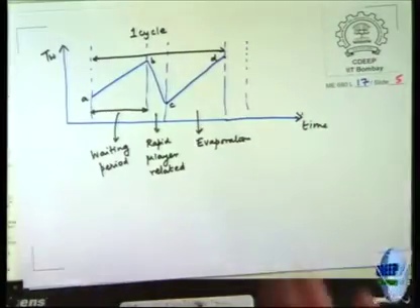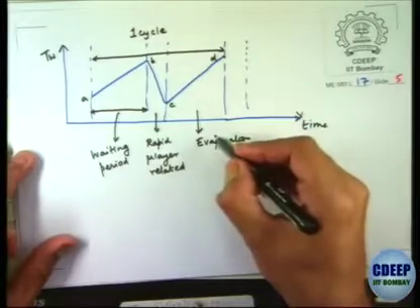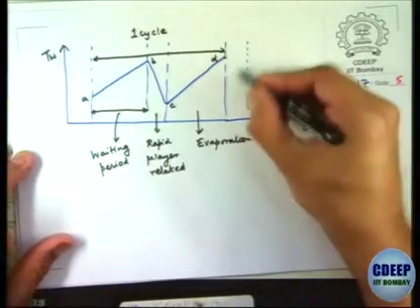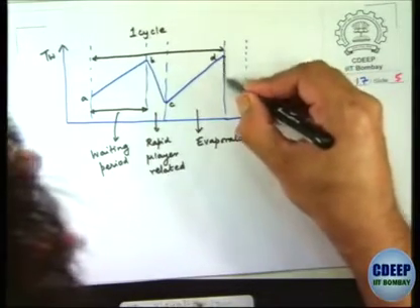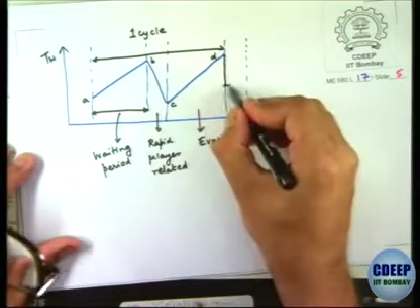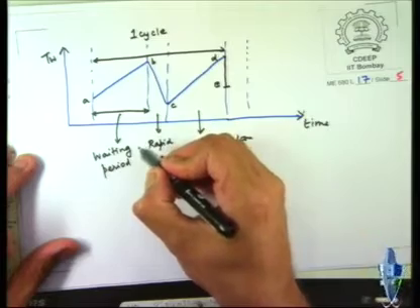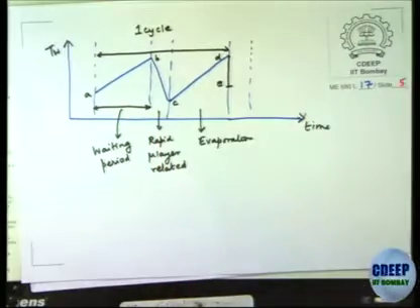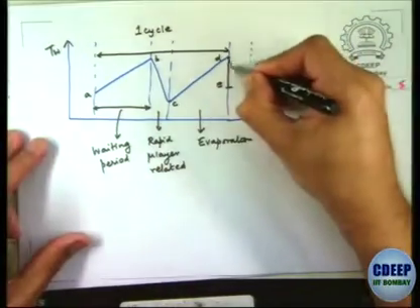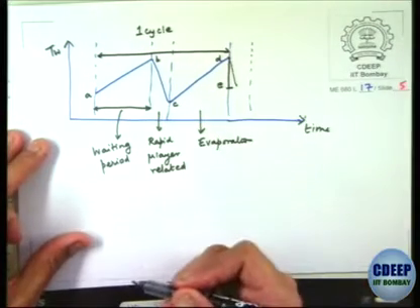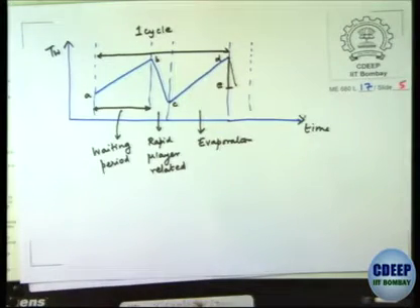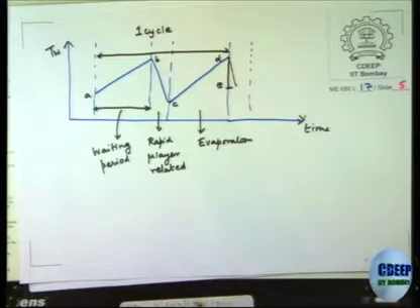Are these four clear? Okay, now what happens after D? It is going to come down instantly to a temperature which is slightly higher than A. Cold fluid is coming, then okay, so put it this way. How does it matter? If it doesn't come down instantly, you are going to have a local dry spot there, which somebody asked last time: CHF doesn't happen or what?